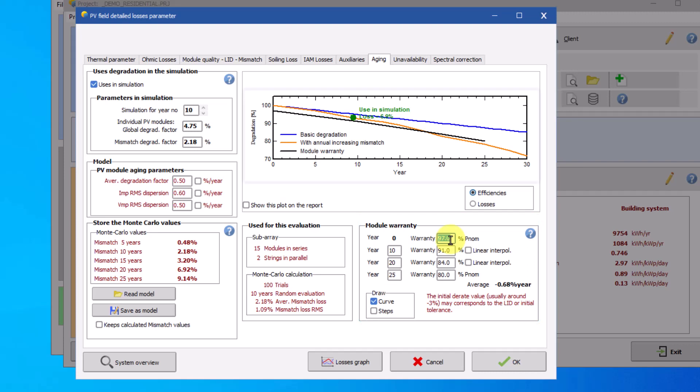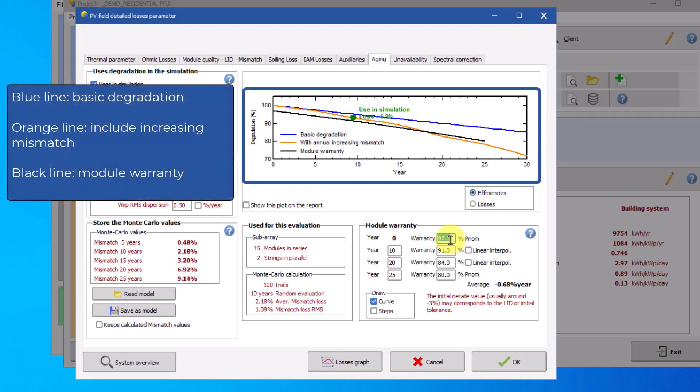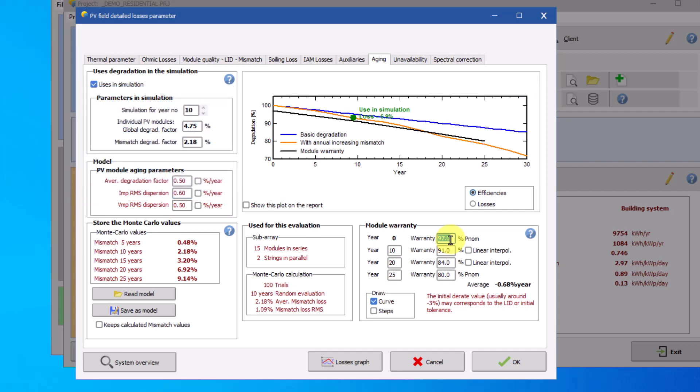These different factors are displayed in the graph on the top right. The basic degradation is represented with the blue line, and the orange line is included in the increasing mismatch losses. The module warranty is then represented with the black line in the graph. The black curve should be below the blue curve due to safety margins. You can choose to represent the evolution of this value with a curve or in steps.